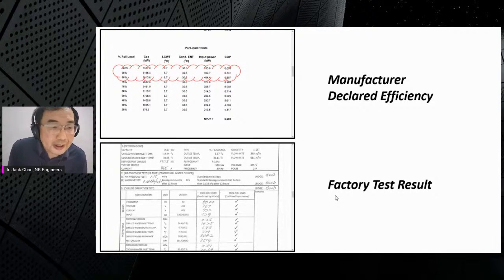They will declare the efficiency, and a sample of the chiller will be brought to the factory to be tested, according to a few standard points where the chiller will operate, and these points will be compared against the declared efficiency. I would suggest that every project performs this test, because it's important. Once the test is passed, then we know that at least the chiller is operating at the rated efficiency. So get the best efficiency you can afford and get this efficiency tested.